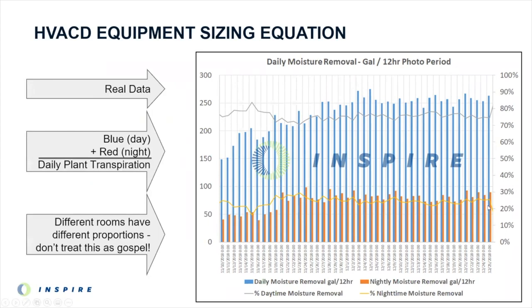The key to this whole equation is the percentage of moisture removed during the day, and to this day we invest a lot of resources to get data from live rooms. The blue bars represent water transpired during the photo period; the red bars represent water transpired or evaporated during the dark period. Add them together and we can see the total daily plant water consumption for that room. More importantly, we see the ratio of lights-on versus 24-hour moisture consumption, and this ratio is the percentage of moisture removal referenced in the previous slide. This is the kind of knowledge that makes sure you're not scrambling to buy portable de-hums that you have to wheel into a room three weeks before harvest.